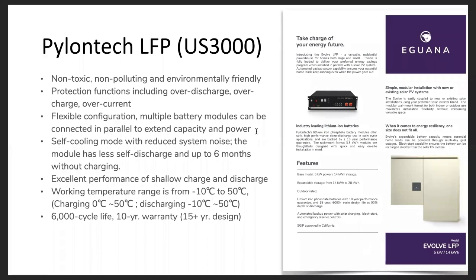So you could start off with a 14 kWh system, for example, for your customers, and a year down the road, the customer says that they want to have a larger capacity system, that you could easily bolt on extra storage capacity, make that bucket bigger without having to add any more inverters to it, or probably in most cases, permitting requirements would be negligible. Don't quote me on that, check with your local AHJs, but just adding extra capacity doesn't change the power component or any of the interconnection requirements. So it makes it easily expandable.